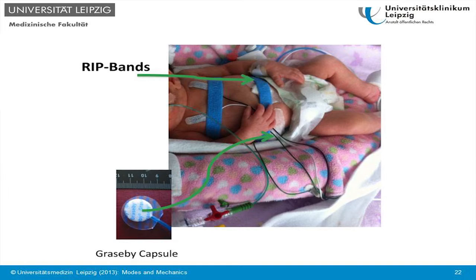Here's a photo. This is a Graseby capsule stuck to the patient right here on the abdomen. So when the patient inhales, the abdomen will rise, and this will increase the pressure in this little pillow here. And through a tube, this pressure increase is transmitted to the ventilator, and the ventilator can then determine that the patient is initiating a breath, and it may be a good time to synchronize it with a machine breath. These are the RIP bands which are sensitive to stretch and will be stretched and generate a signal when the patient inhales and the chest expands.